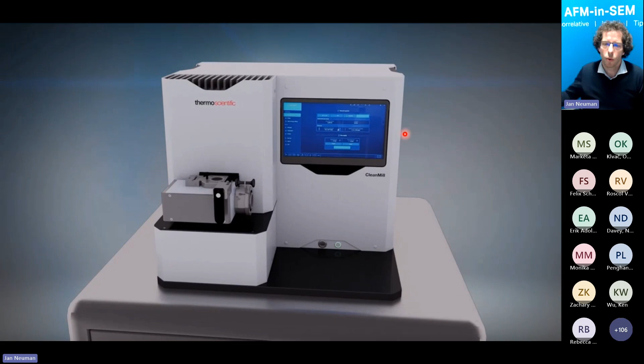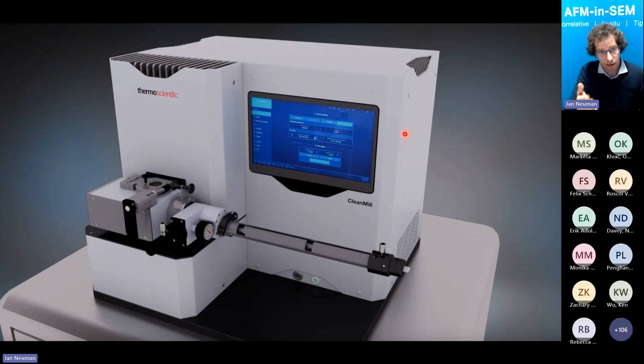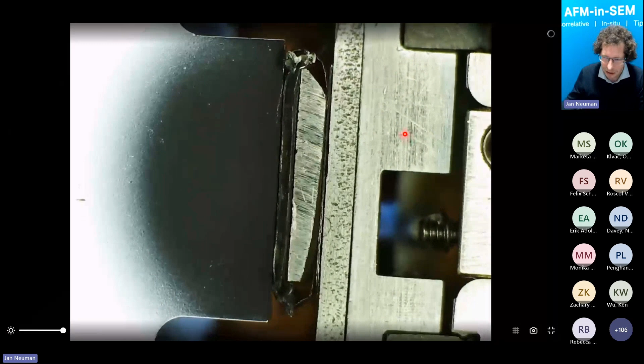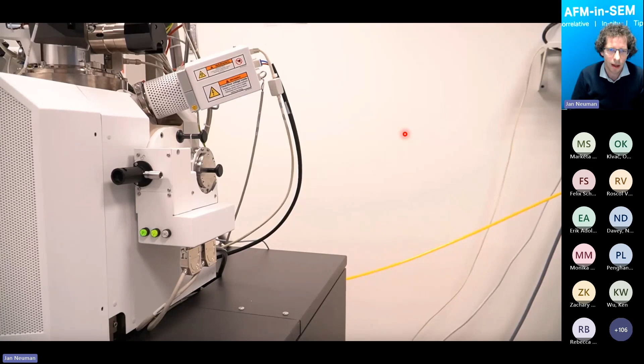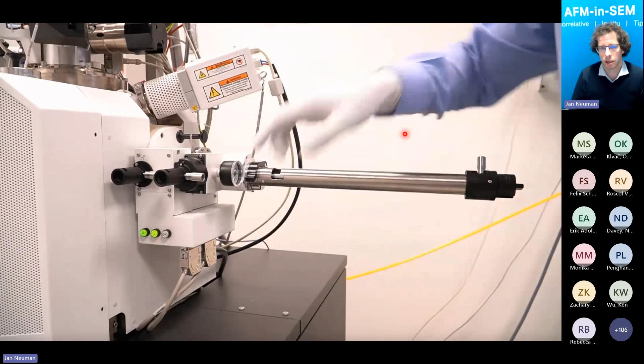And now we are ready to take this part into the broad ion beam milling, in this case the Clean Mill, where again the process is optimized so that no exposure occurs. In the broad ion milling, we take the sample and polish it with the broad ion beam, and after that, again, you can use a Clean Connect and bring the sample after the cross-section preparation into the electron microscope.